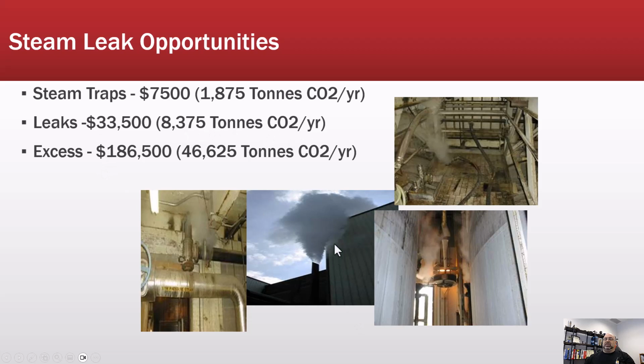And then excess energy, whenever you see steam blowing out a pipe constantly in the plant, that just means it fell under the pressure. So in this case, the lowest pressure they used was 40 psi. What was coming out of here was roughly 20 psi, and hence the plume. That's not contamination, that's literally moisture. That excess being blown out is potentially worth $186,000, or almost 47,000 tons of CO2 per year, which is ridiculous. That's 47 kilotons of CO2 per year blown out stacks. Why not take that, recompress it, and reuse it?